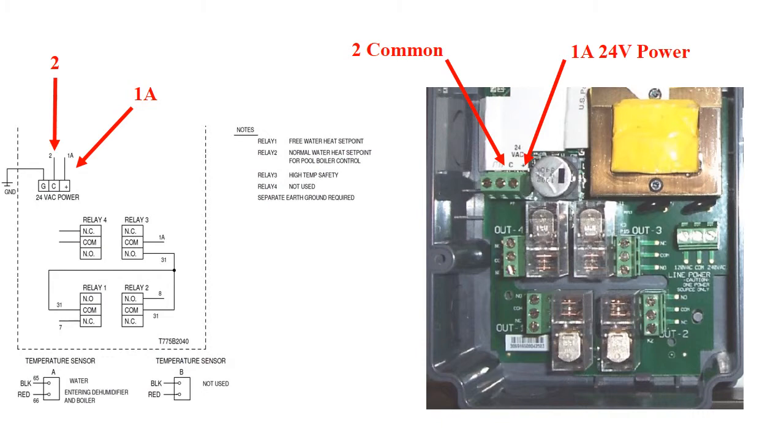On the power strip schematic, you will notice here a number 1A next to the wire protruding from the positive terminal. This means that that terminal connects to a number 1A terminal on the dehumidifier. The number 2 next to it on the C or common means that it is to be connected to a number 2 terminal, and so forth for all connections.